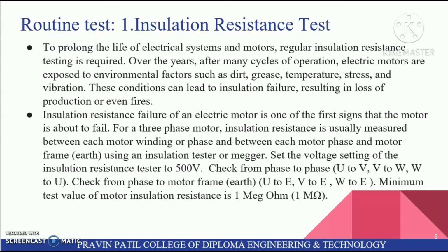So first is routine test. In this first is insulation resistance test. To prolong the life of electrical systems and motors, regular insulation resistance testing is required. Over the years, after many cycles of operation, electric motors are exposed to environmental factors such as dirt, grease, temperature, stress, and vibration. These conditions can lead to insulation failure, resulting in loss of production or even fires. Insulation resistance failure of an electric motor is one of the first signs that the motor is about to fail.